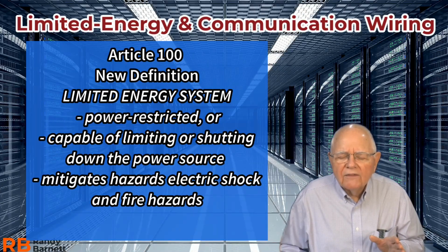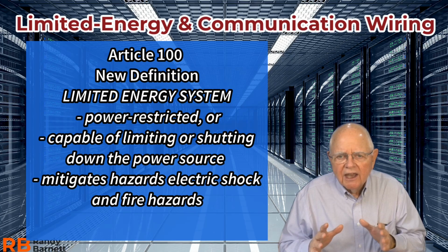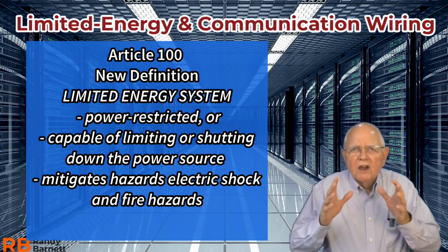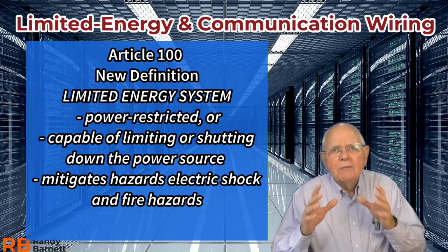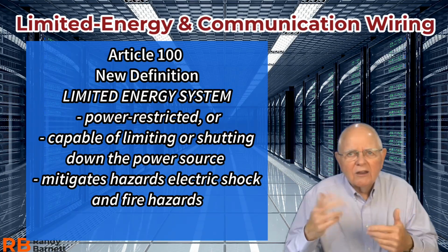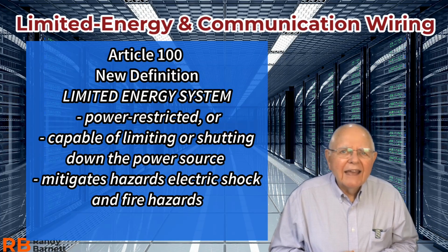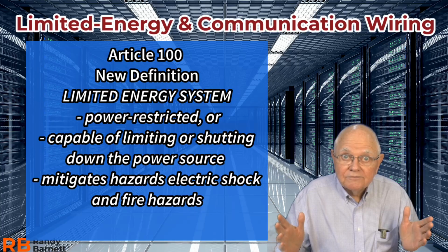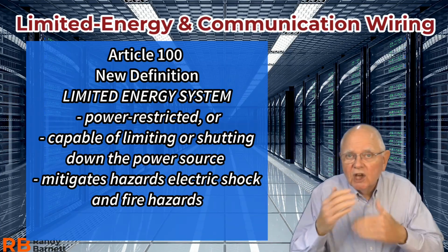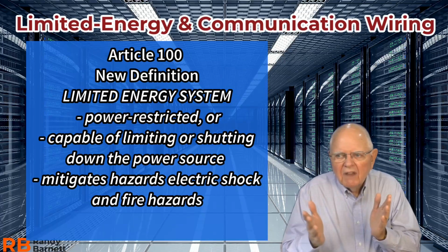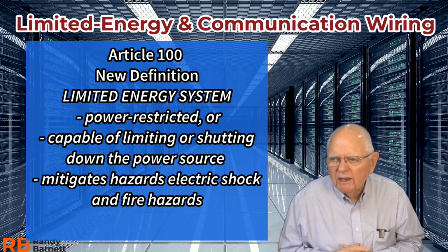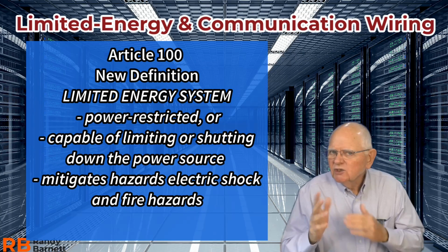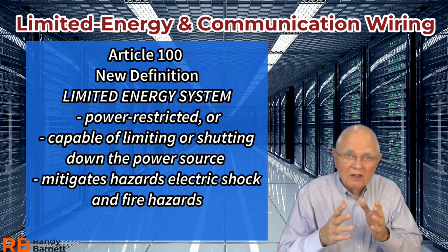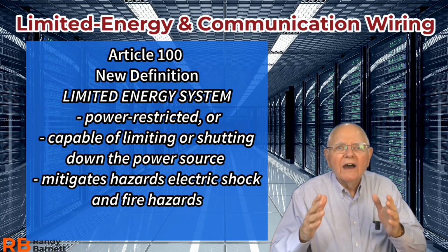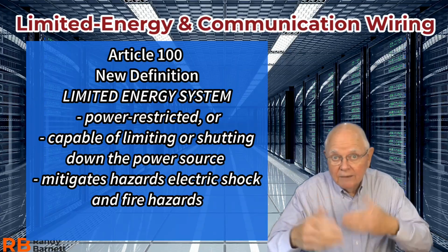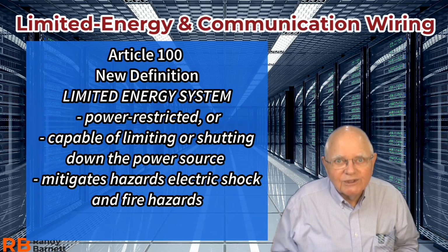In Article 100, we have the definition for limited energy systems. And here's what it revolves around. It talks about these limited energy systems being somehow power restricted, or they somehow limit or shut down the power to mitigate the hazards of shock and fire. So it kind of makes sense. If I install a system and under normal conditions, I wouldn't expect to get a shock from it, even if I touched an energized conductor, and there's really not enough energy there in order to cause a fire, maybe I don't need to follow all of those same installation requirements that I might have to on a 240 or a 480 system, something like that, certainly.